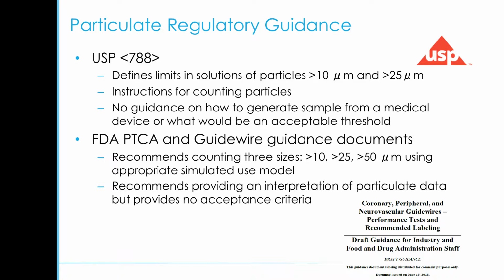FDA has put out several guidance documents, one for PTCA catheters and another for guide wires, where they recommend counting not just in 2 different size bins, but 3: greater than 10 micron, greater than 25, and even greater than 50 micron, using an appropriate simulated use model. That simulated use model is up to the manufacturer's discretion to have a relevant one. They also recommend providing an interpretation of the particulate data. The challenge is they don't provide what exactly the acceptance criteria is. So there is some uncertainty, and I want to go through some of the challenges and considerations for doing particle testing.